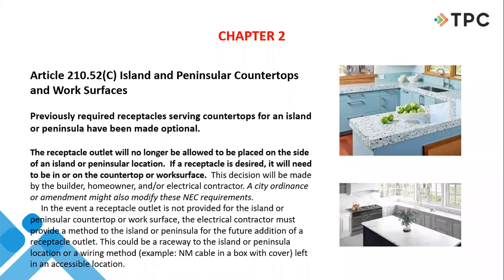This one's going to get interesting for you guys in the residential world. The code previously required receptacles serving countertops for an island or peninsula. That whole thing has now been made optional. The outlet will no longer be allowed to be placed on the side of an island or a peninsular location. If a receptacle is desired, it'll need to be in or on the countertop or work surface. City ordinances or amendments may modify this code requirement. In the event a receptacle outlet is not provided for the island or countertop or work surface, the contractor must provide a wiring method to the island or peninsula for future addition of an outlet, raceway, cable, whatever the case may be.